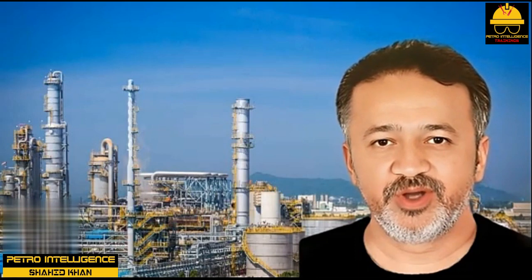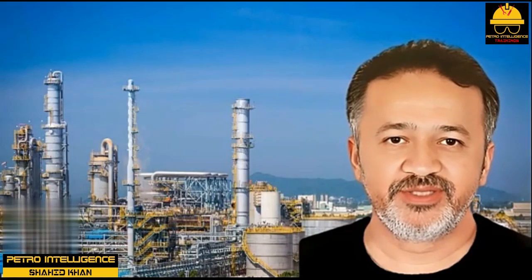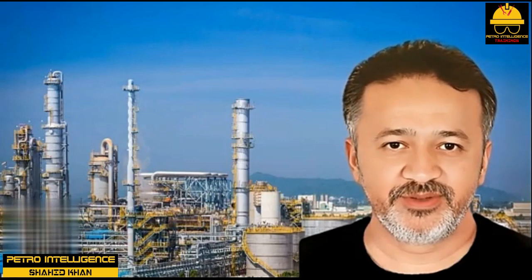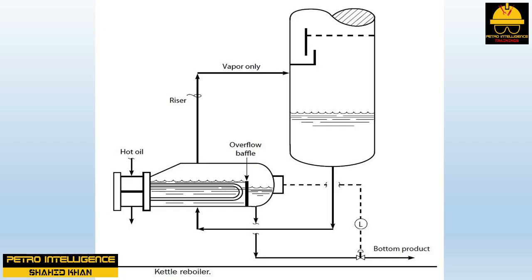Reboilers are sometimes inserted into the bottom of a tower — these are called stab-in reboilers. It is not ideal because it makes it more difficult to fix a leaking or fouled reboiler without opening the tower. The kettle reboiler has essentially the same process performance characteristics as the stab-in reboiler but is entirely external to the tower. In a kettle reboiler, the bottoms product level control valve does not control the level in the tower; it controls the level on the product side of the reboiler only. The liquid level on the boiling side is controlled by the internal overflow baffle.